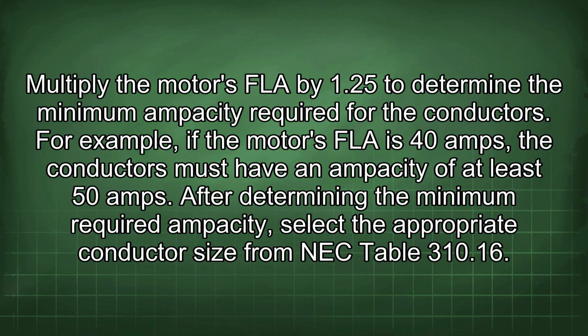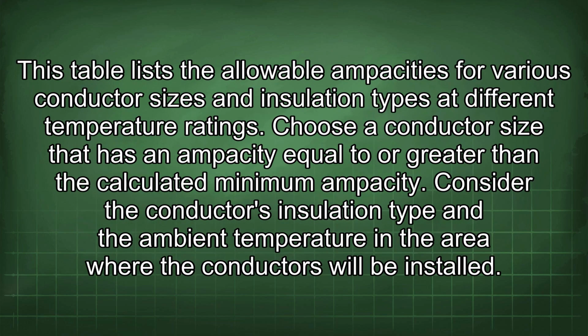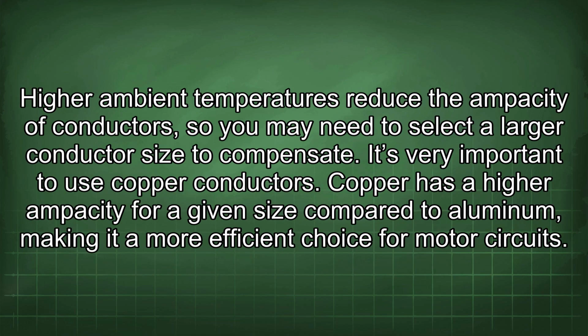After determining the minimum required ampacity, select the appropriate conductor size from NEC Table 310.16. This table lists the allowable ampacities for various conductor sizes and insulation types at different temperature ratings. Choose a conductor size that has an ampacity equal to or greater than the calculated minimum ampacity. Consider the conductor's insulation type and the ambient temperature in the area where the conductors will be installed. Higher ambient temperatures reduce the ampacity of conductors, so you may need to select a larger conductor size to compensate.